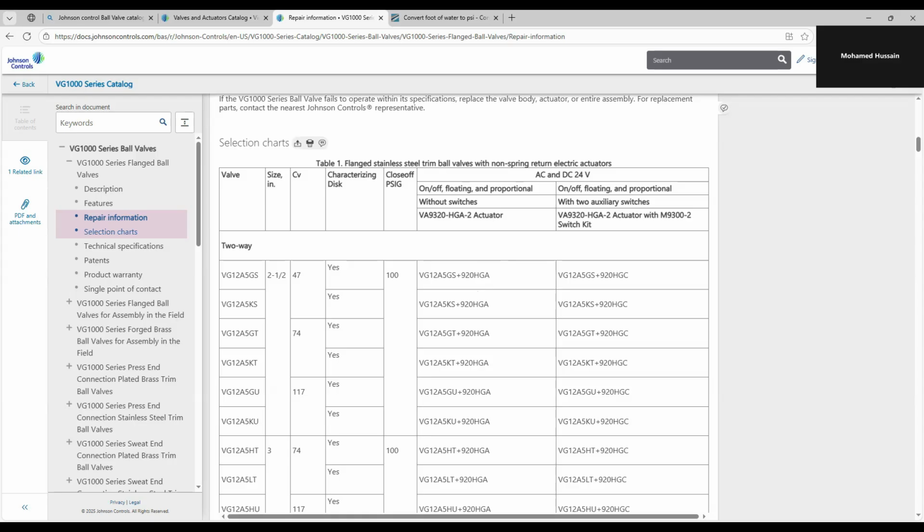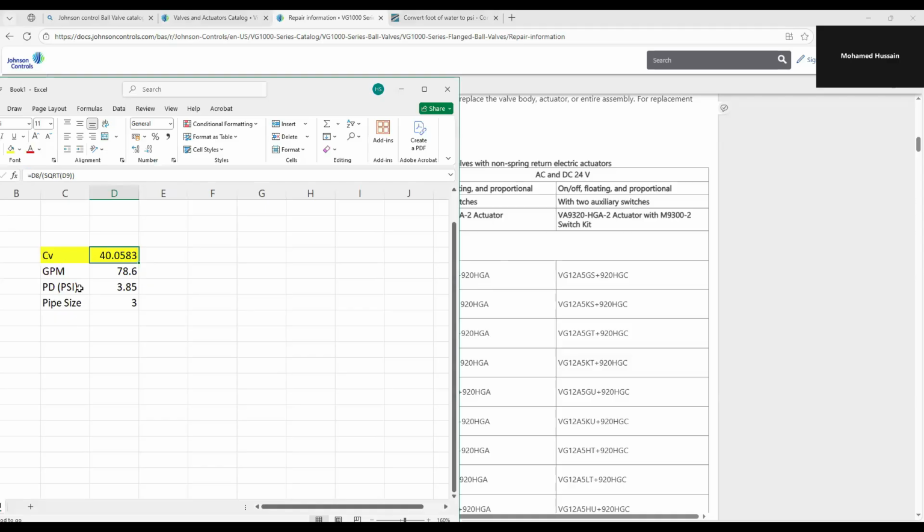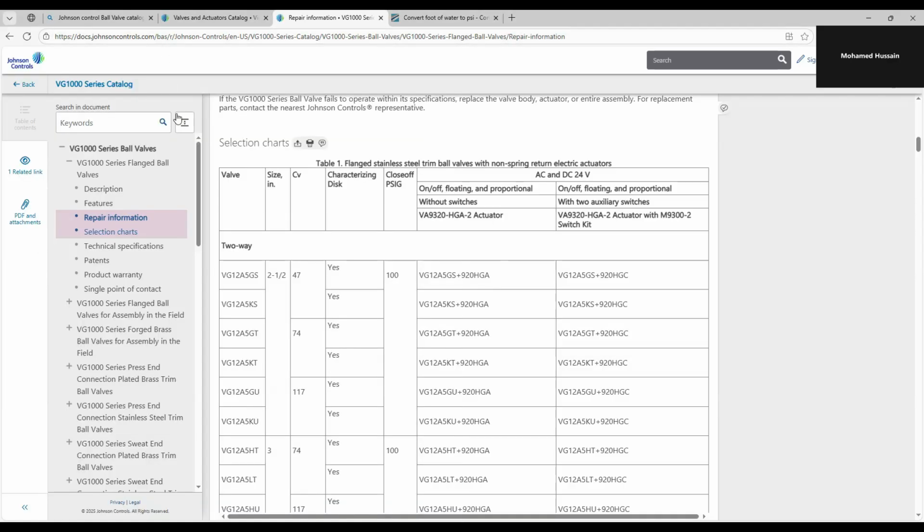So we have sized the valve with the calculated CV based on the inputs. We opened that Johnson Controls. Same thing for Honeywell controls catalog. Same thing for Belimo. Same thing for Schneider, Siemens. Same thing. You just have to mention that because global valve types are similar. Ball valve means all will call it ball valve only. No one calls a ball valve something like a gray valve or sine valve. Ball valve means ball valve. You have to be careful reading this information. That is very, very important.